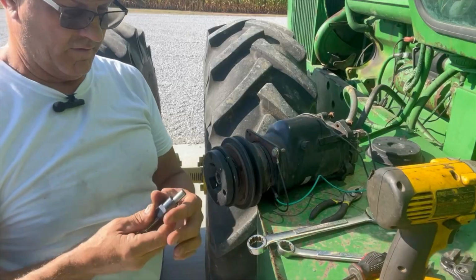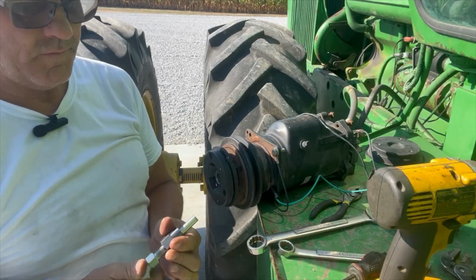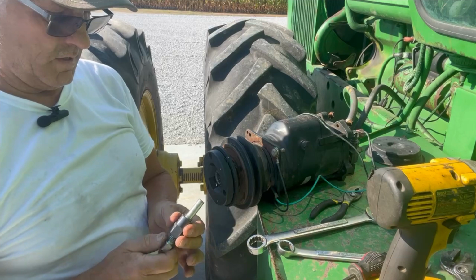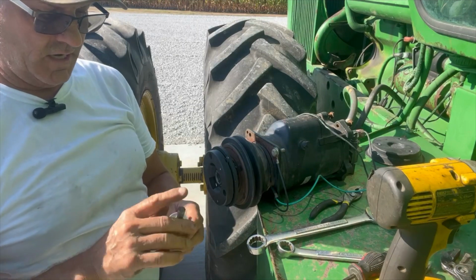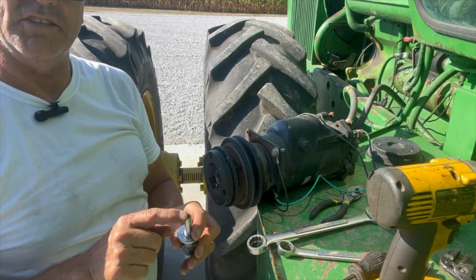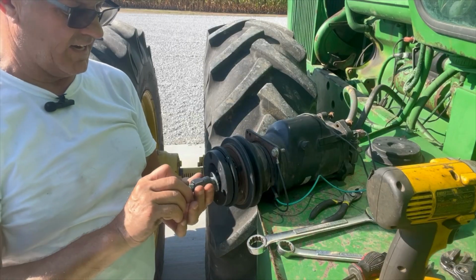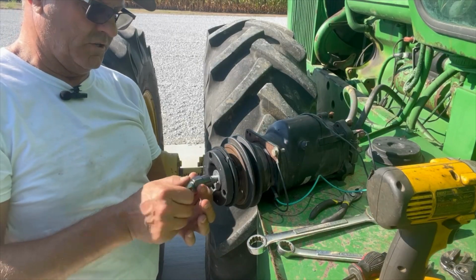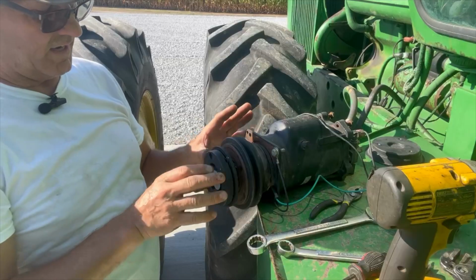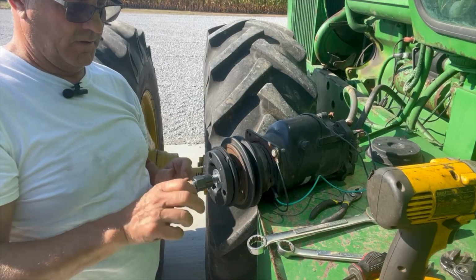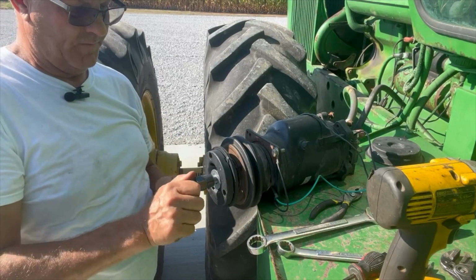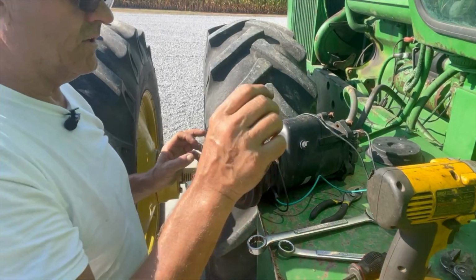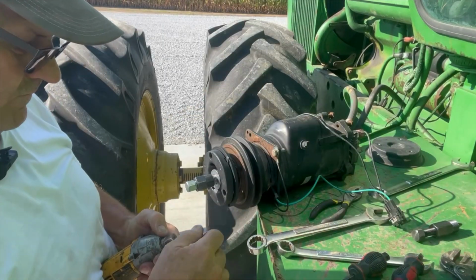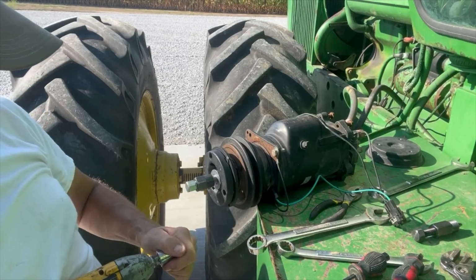Make sure it's in there, and then the installation tool - it screws on the end of the compressor shaft on the inside, because you don't want to pound on this to get it on, because you will damage the compressor doing that. So I'm going to torque that on just a bit so it holds.